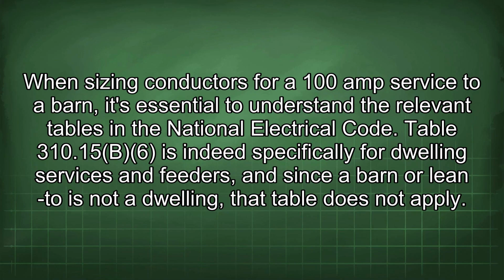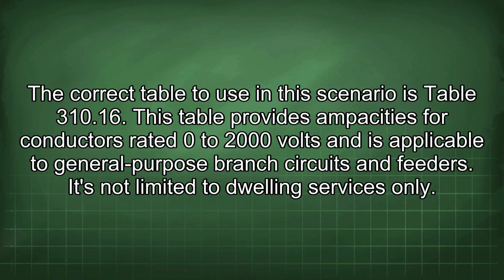When sizing conductors for a 100 amp service to a barn, it's essential to understand the relevant tables in the National Electrical Code. Table 310.15(B)(6) is indeed specifically for dwelling services and feeders, and since a barn or lean-to is not a dwelling, that table does not apply. The correct table to use in this scenario is Table 310.16.